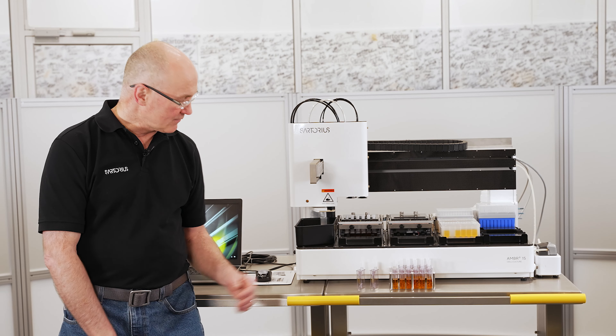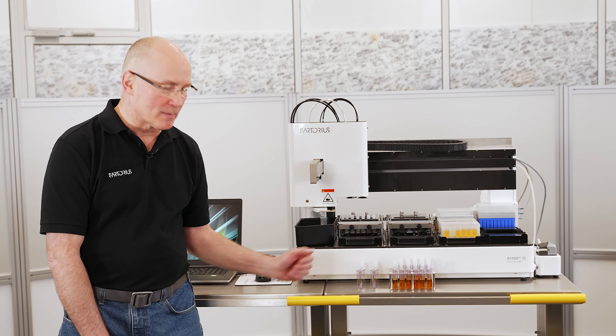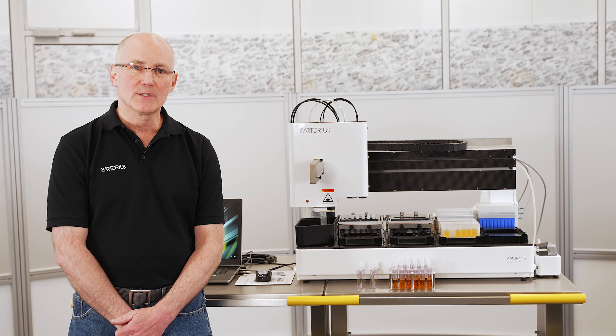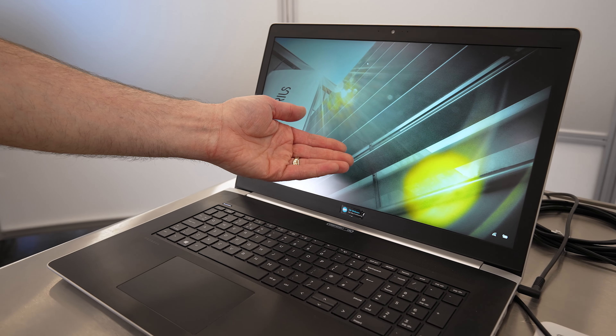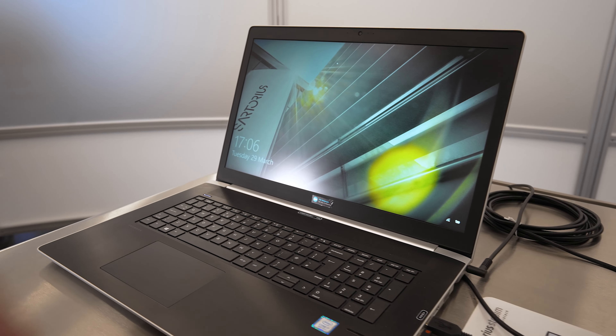The three main components of the ambr 15 cell culture system are the 10–15 ml micro bioreactor, the workstation, and the control computer with its powerful, easy-to-use software. There is no code writing, and process building is all drop-down menu driven.